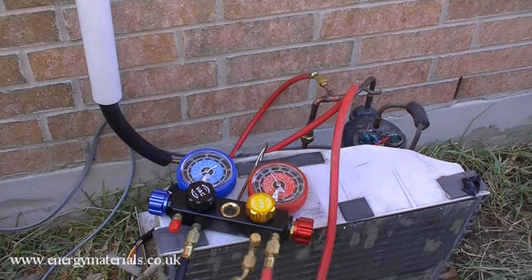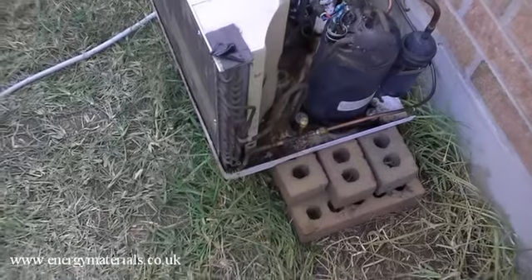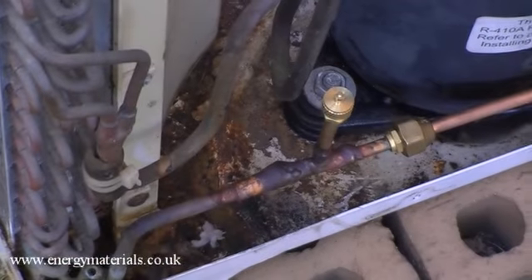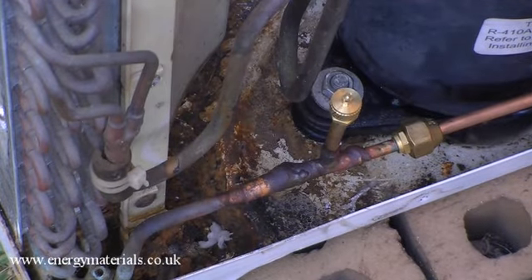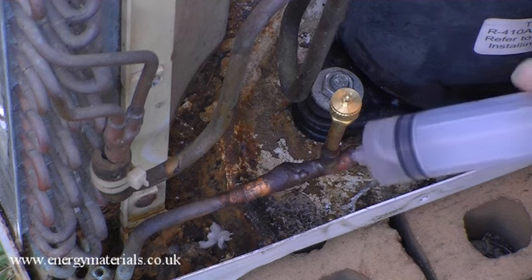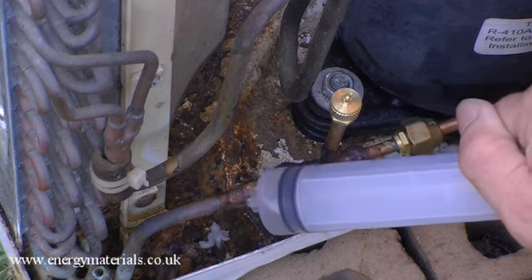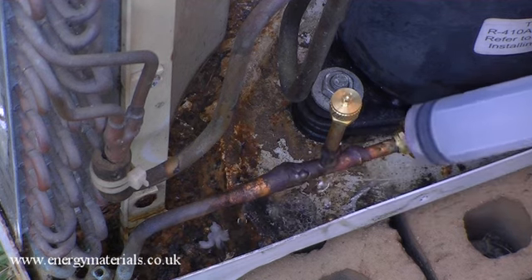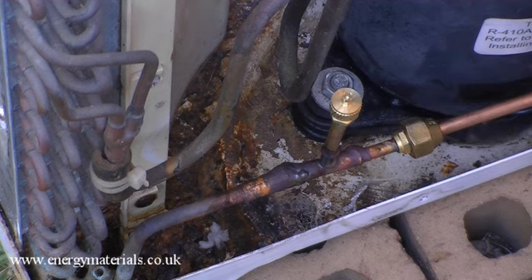So I've pressurized it to about 300 psi or 20 bar, and now I'm going to check the fittings. Not the tiniest braze joints in the world, but the easiest way to check is to get some soap solution and apply it over the braze joints. Definitely over this fitting. And we'll wait 5 minutes and we'll look for bubbles. And if we find bubbles, then we need to rework the joint.